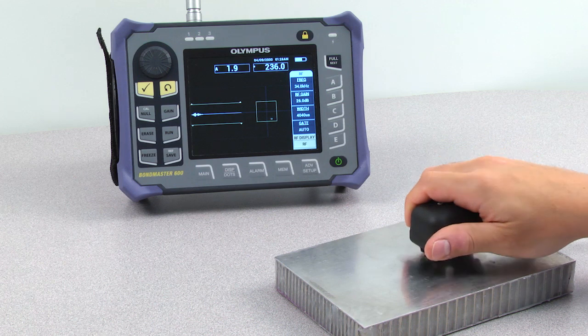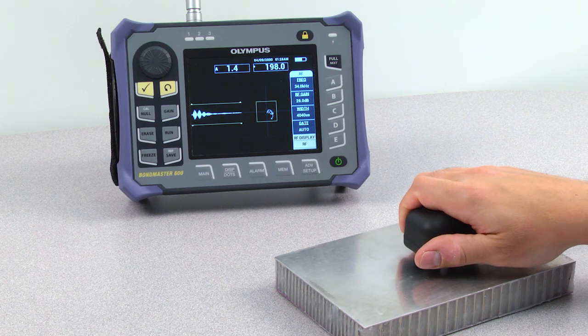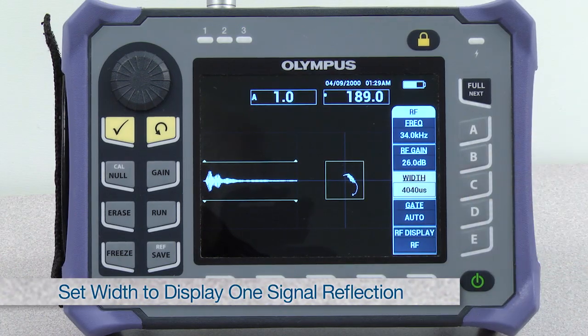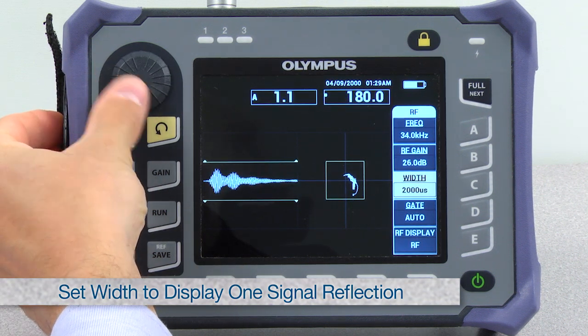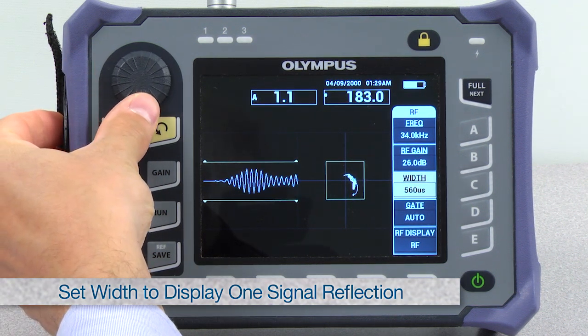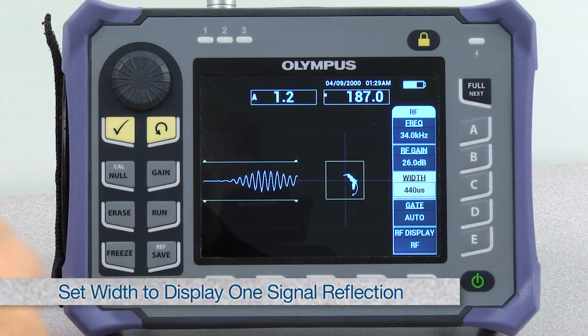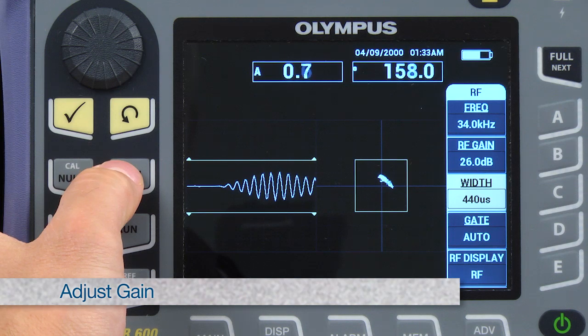Put the probe on a defect-free area and maintain it. Set the width in order to visualize only one signal reflection. Typically, only the first sound reflection has true interest and subsequent reflections show less stability and repeatability. Adjust the gain as needed.